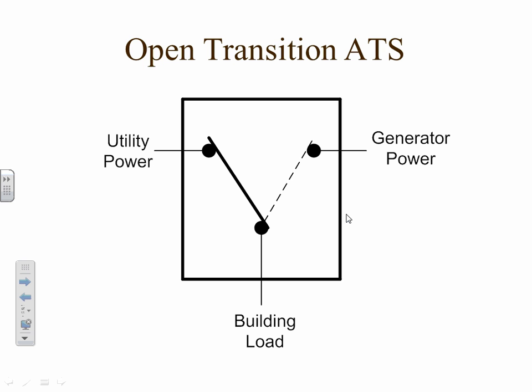So if we switch it back over to the utility, we've now gone from full load on the generator to no load. That exhaust temperature correlates, so the exhaust temperature comes down pretty quick. So they use that relatively cooler air to run through that turbocharger to cool it down gradually, because they're really expensive. So that's a time delay on stop. A lot of customers will call, and that's typically about 10 minutes is what our technicians set them for. They can be a little longer, but 10 minutes you're going to be running.